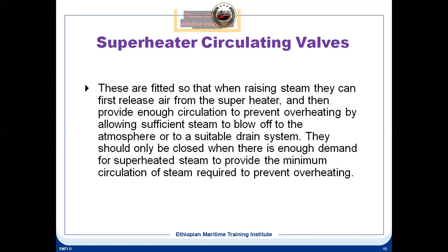So that means in your superheater, let's say your turbine is not working, that means the steam which is being raised in your superheater is not being consumed. If the steam is not being consumed, that means it can lead to overheating. So you need to have enough circulation, and that's where these superheater circulating valves come into being.